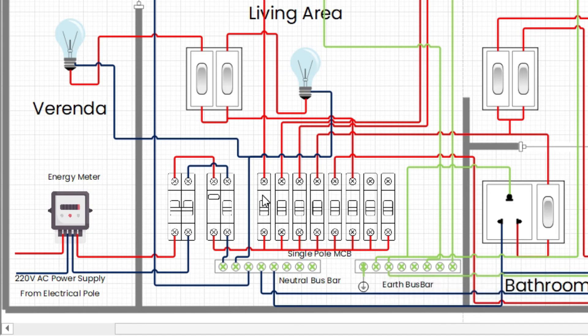From ELCB, the phase wire is connected to all single pole MCBs, and the neutral wire is connected to the neutral bus bar. From the single pole MCB, the phase wire is connected to the living area, dining area, bedroom one, master bedroom, kitchen, and bathroom.